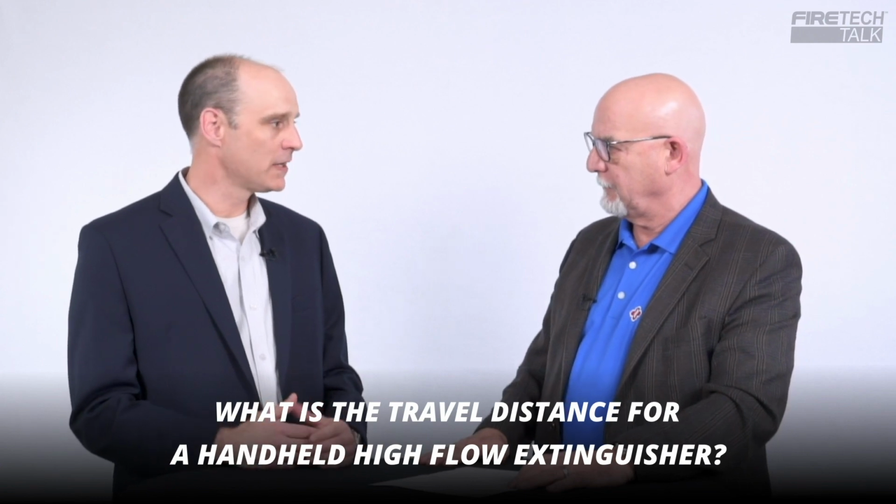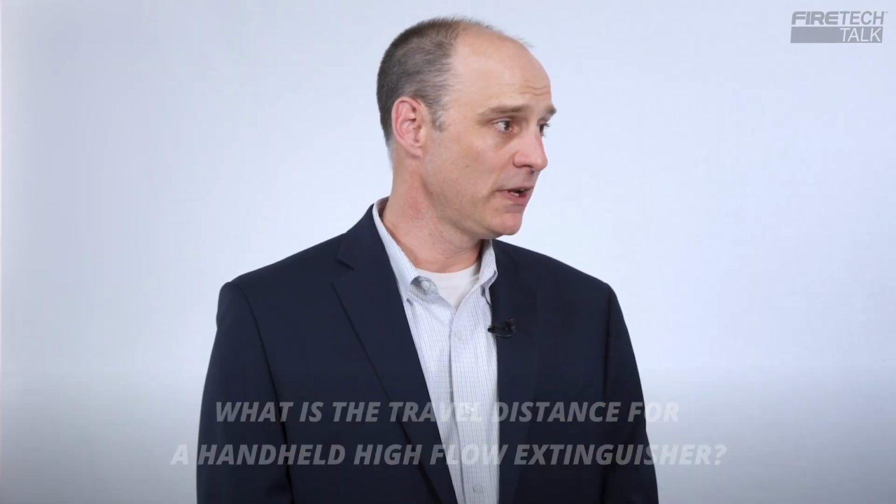What is a travel distance with a handheld high-flow extinguisher? So typically a compliant extinguisher would be 30 or 50 feet, depending on what type of Class B hazard you have. With a high-flow extinguisher, we already know that that is an extra hazard, and because it's an extra hazard, we're going to limit travel to no more than 30 feet. All right, so is this a supplemental fire extinguisher? This extinguisher will meet the requirements for that hazard. Okay, gotcha.